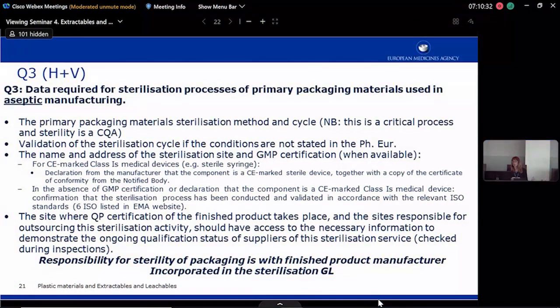But what about the data for the sterilization process of the primary packaging material used in aseptic manufacturing? So if at the end the applicant justifies the use of aseptic manufacturing, what do we need to see? Sometimes this is not always assessed in such detail. So it's good to keep in mind that we need to have the primary packaging material sterilization method and cycle, because it's a critical process and sterility is considered a critical quality attribute.